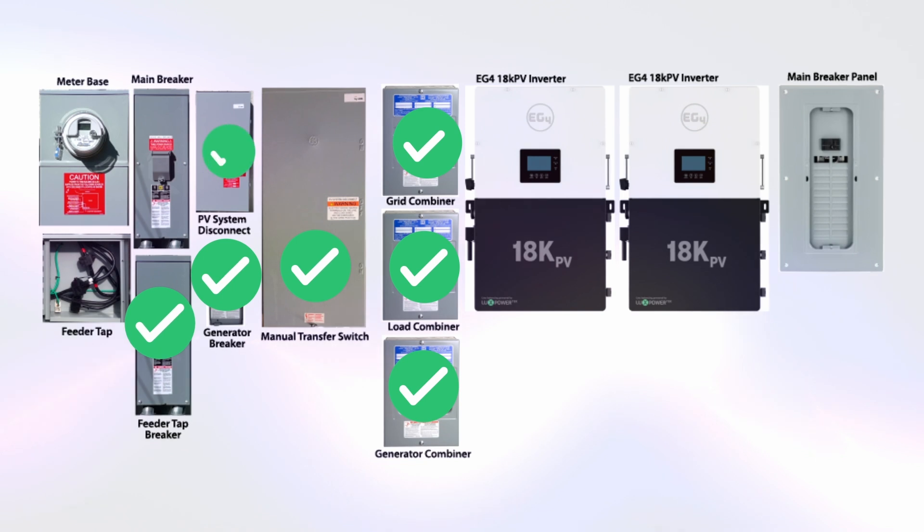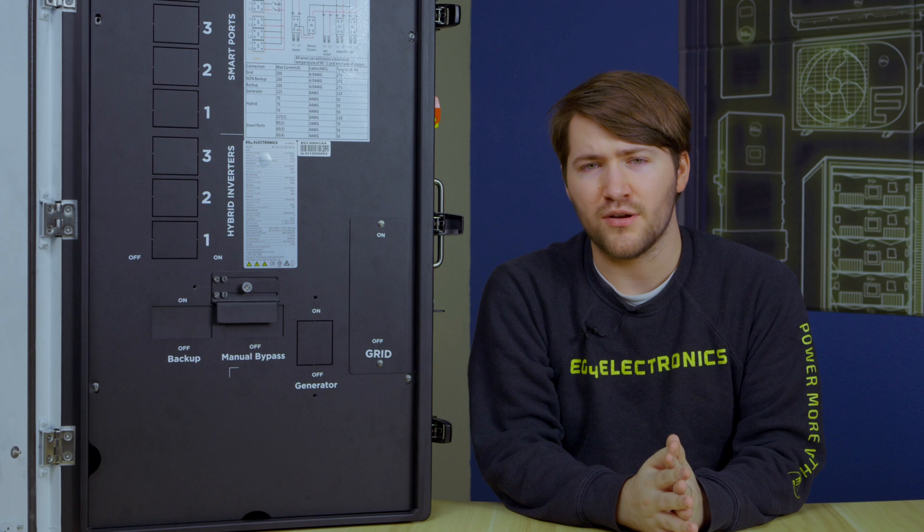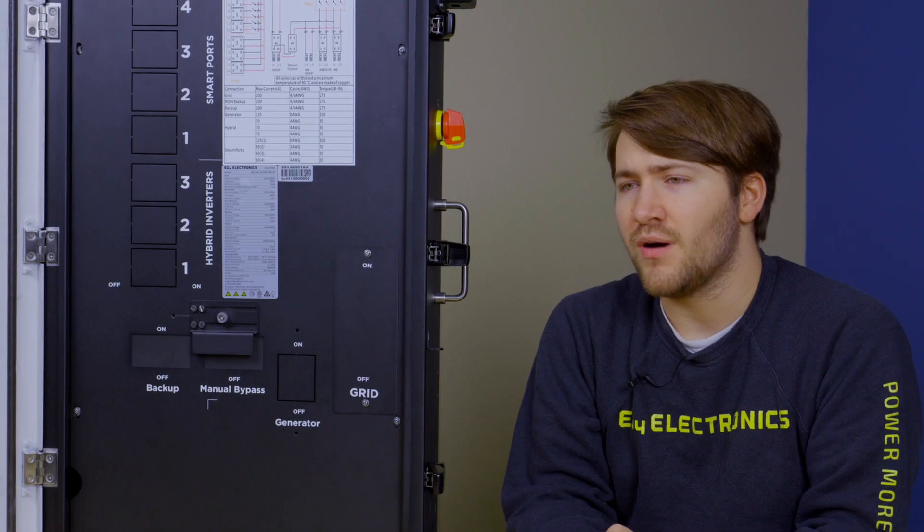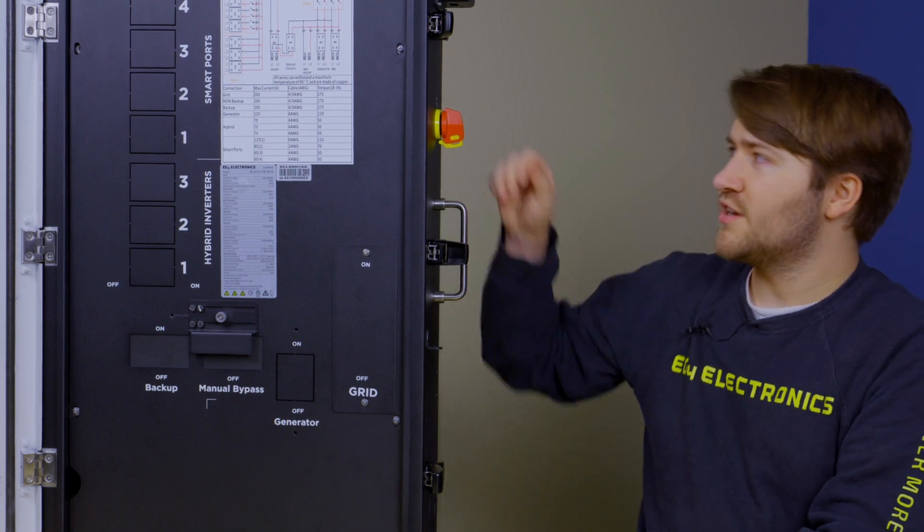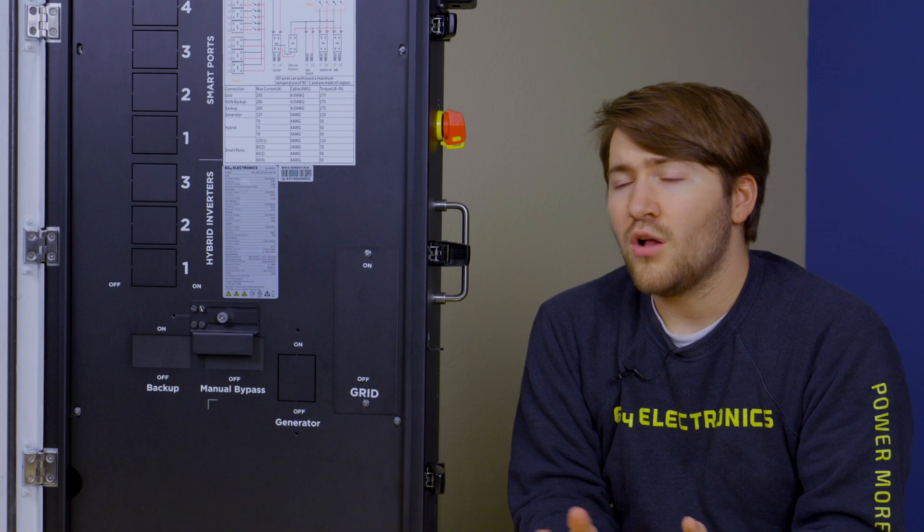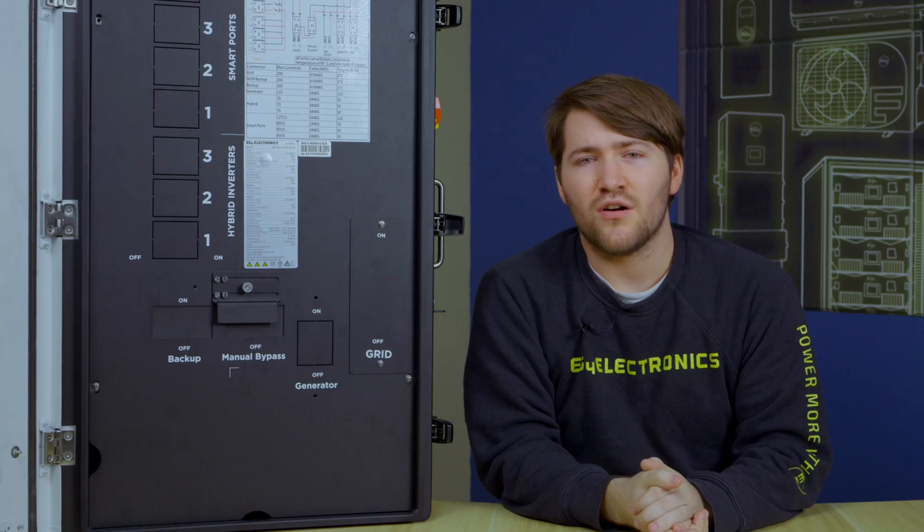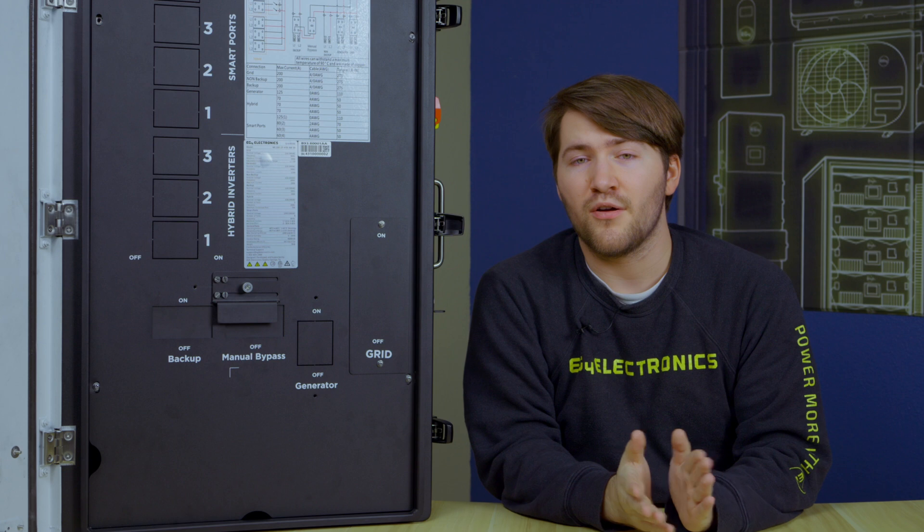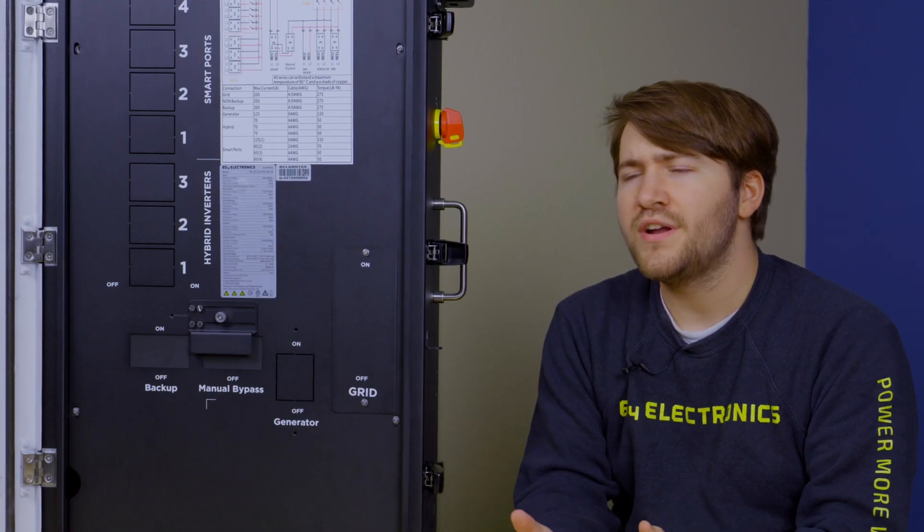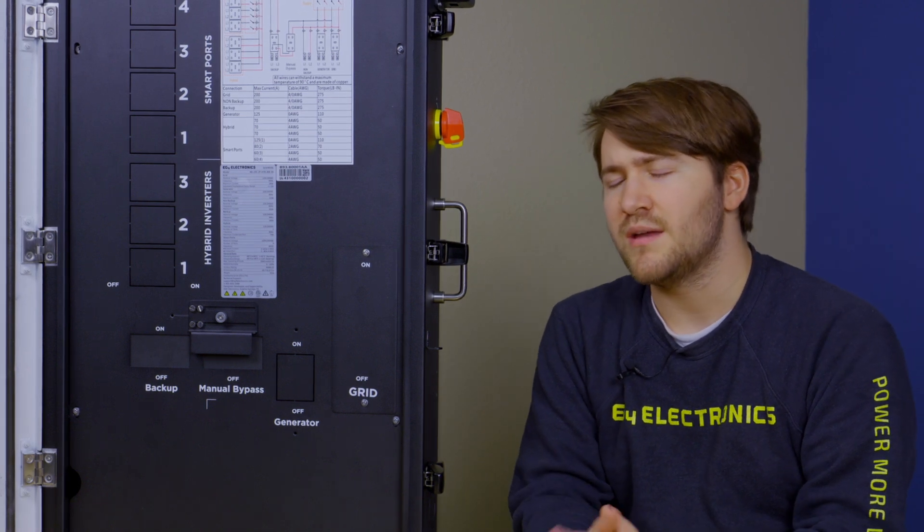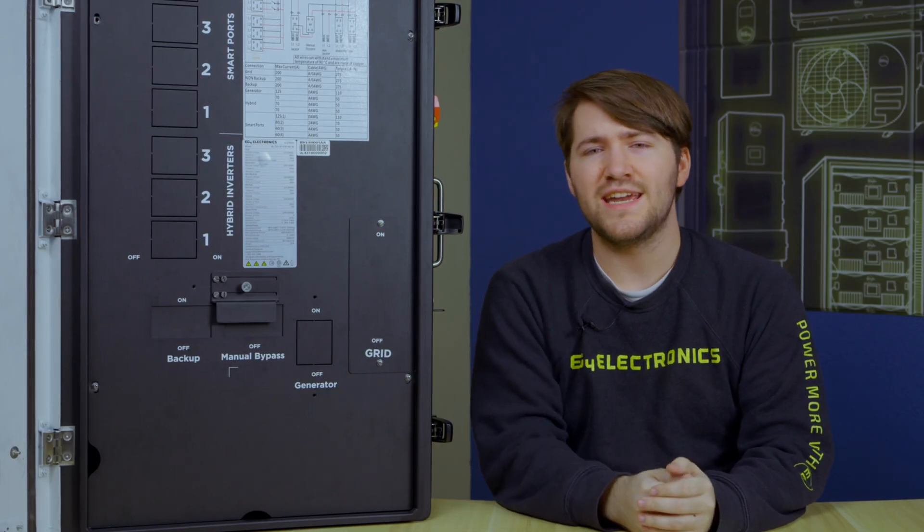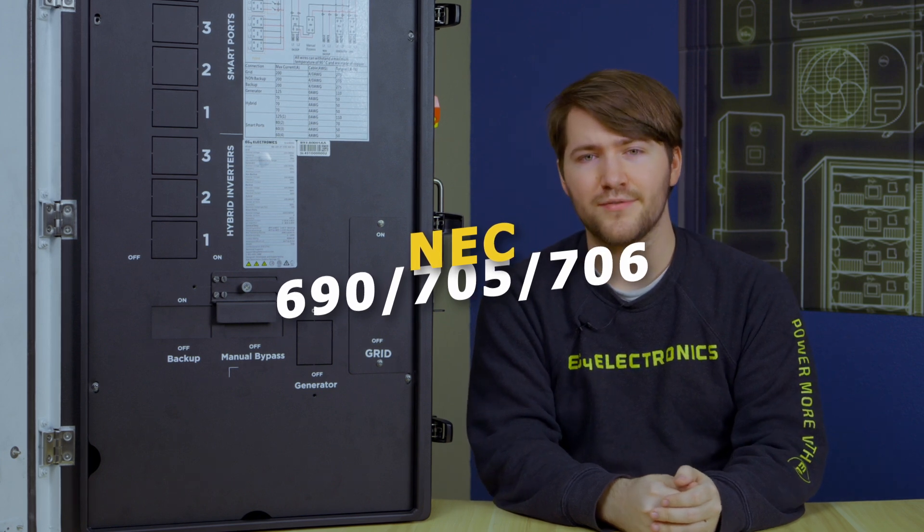You also don't need the PV system disconnect anymore as all of the RSD or rapid shutdown systems are included within the grid boss itself. By activating the rapid shutdown on the grid boss, all of the systems in your BESS that are EG4 will shut down automatically, even your batteries with the TRSD. All the various code compliances and the systems that are in the image that we just showed can be found in NEC 690, 706, and 705.